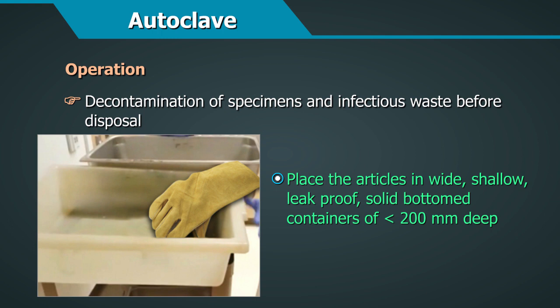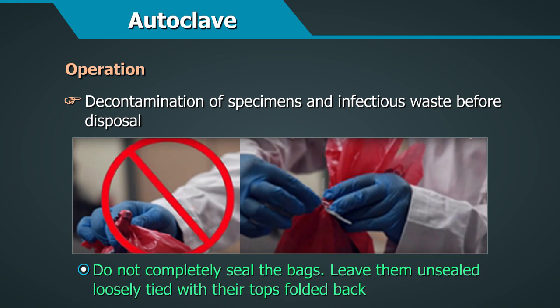For decontamination of specimens and infectious waste, place articles in wide, shallow, leak-proof, solid-bottomed containers not more than 200 mm deep. Do not cover the containers. When decontaminating infectious material in plastic bags, do not overpack the bags — leave them unsealed with their tops folded back.